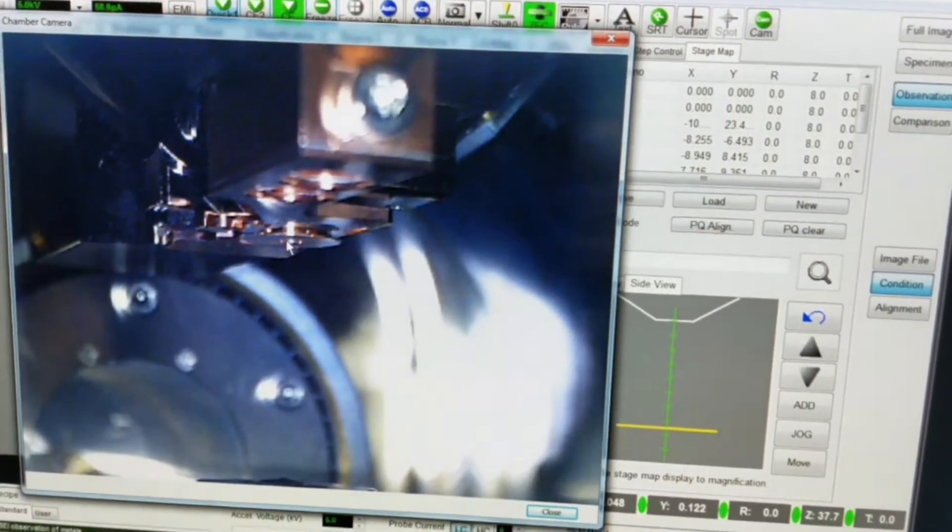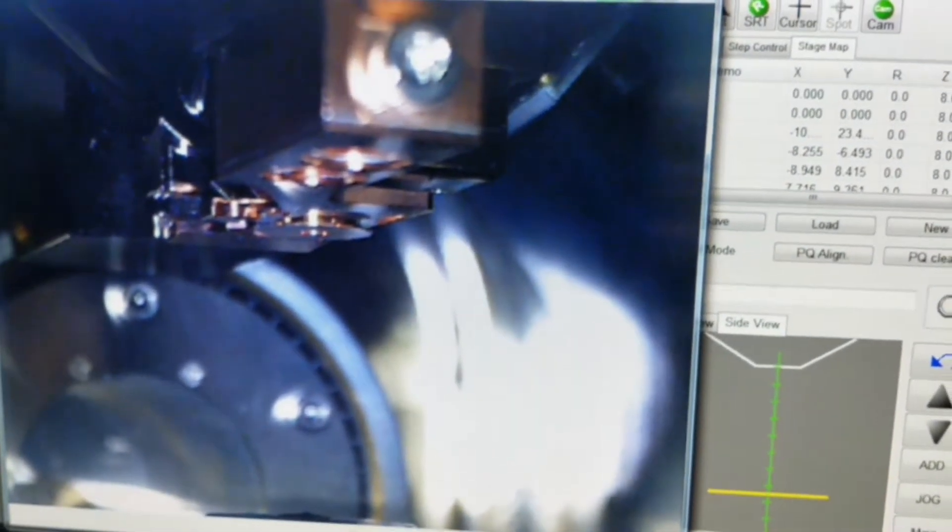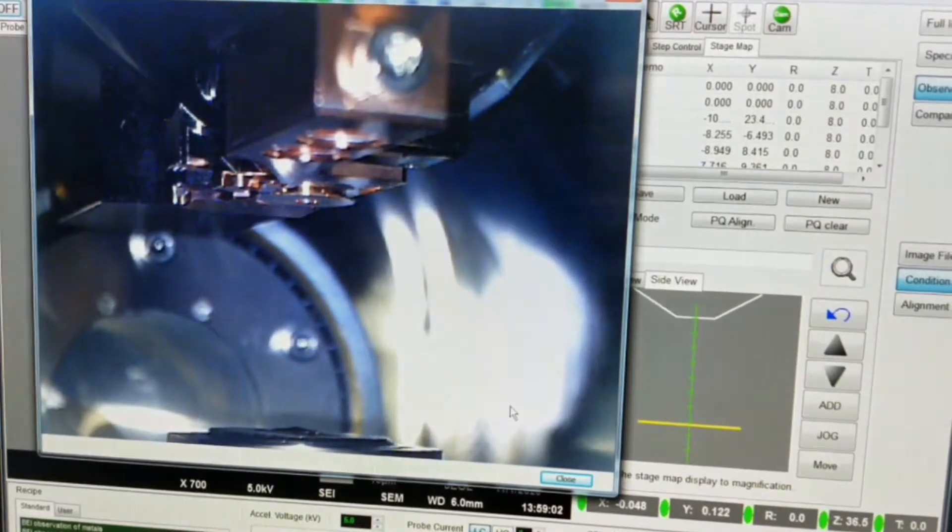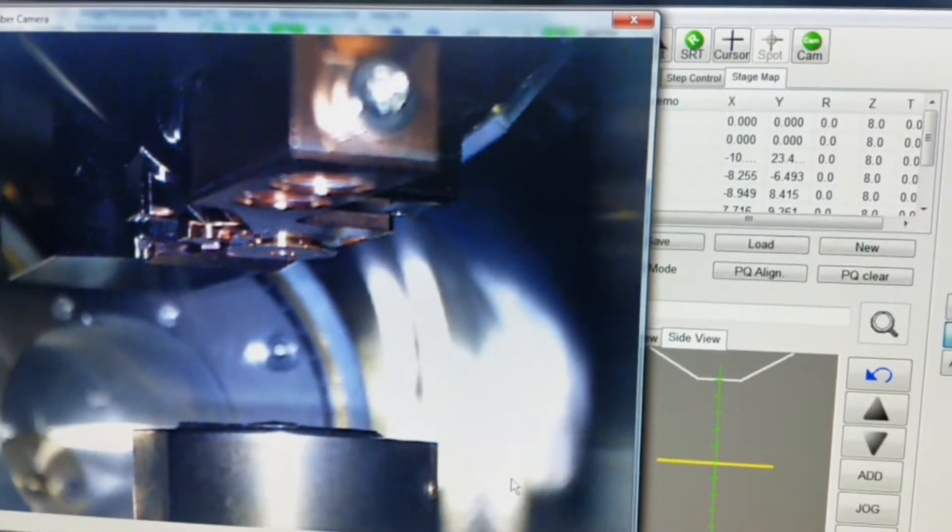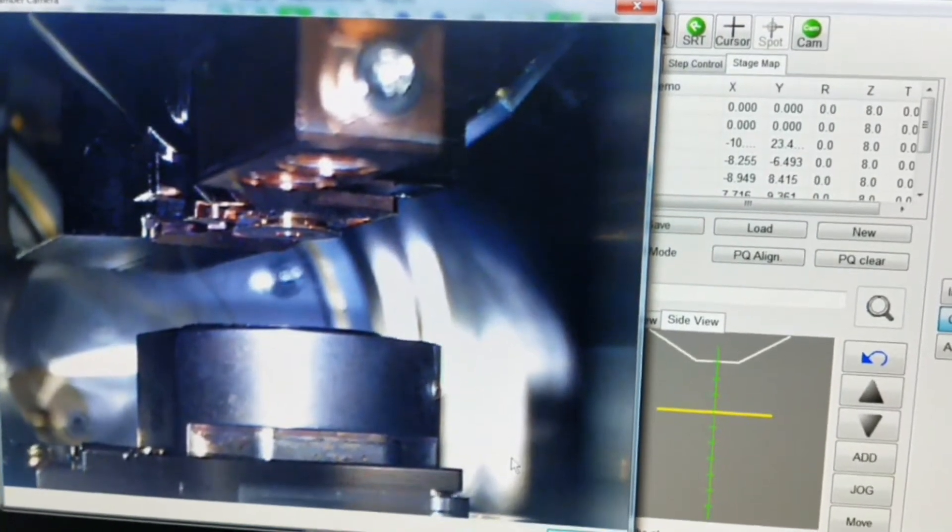Now I am going to take the stage a little bit upward. This is the objective, and this is the specimen that we have with the specimen holder. We need to make it a little bit closer to the objective, so we have to reduce the working distance. You may see the substrate holder is getting closer to the objective. It is not required all the time that we need to keep the substrate holder close to the objective.